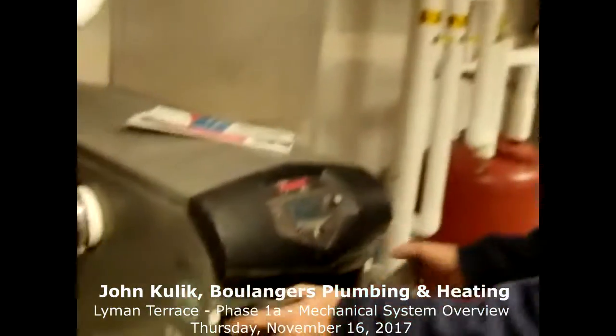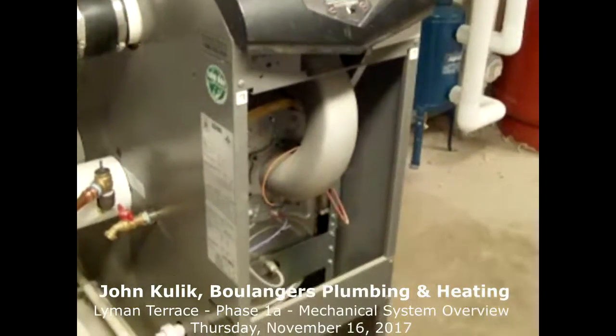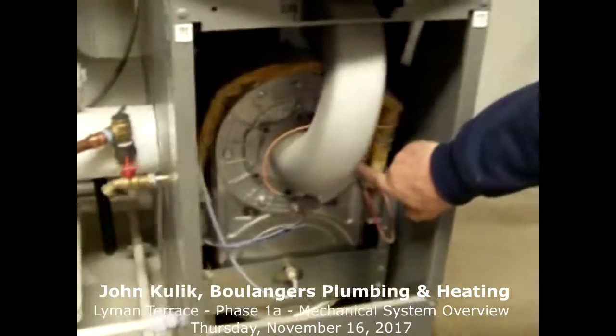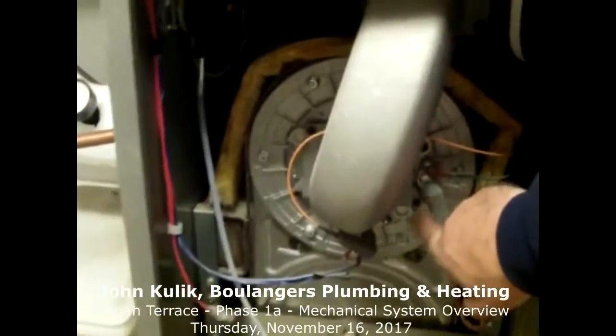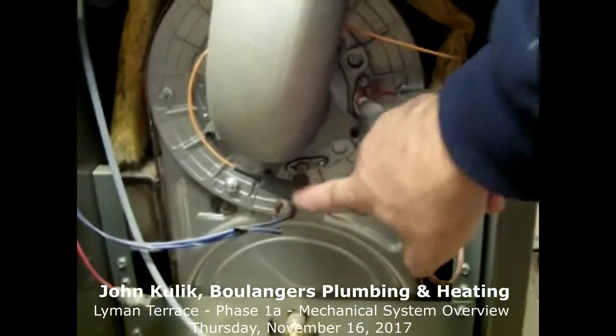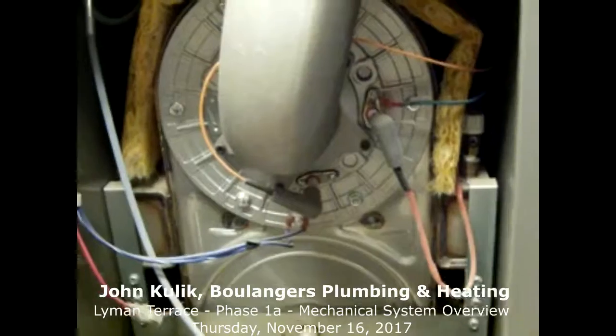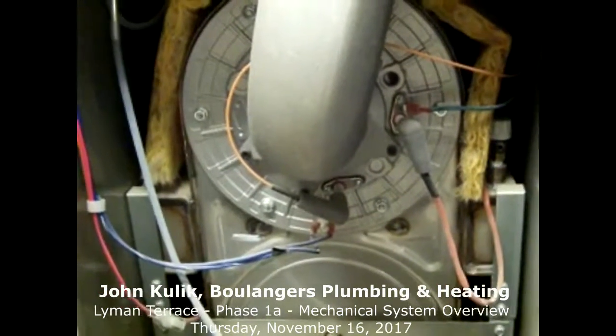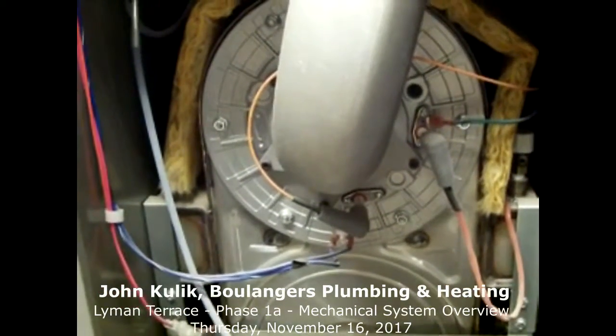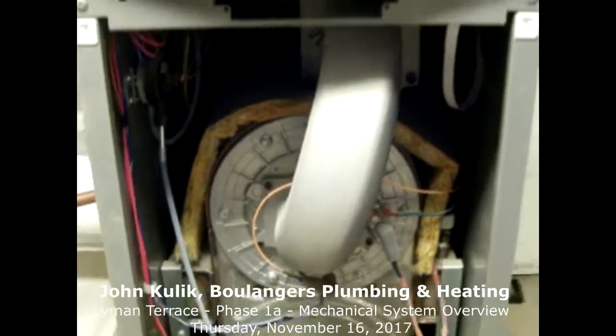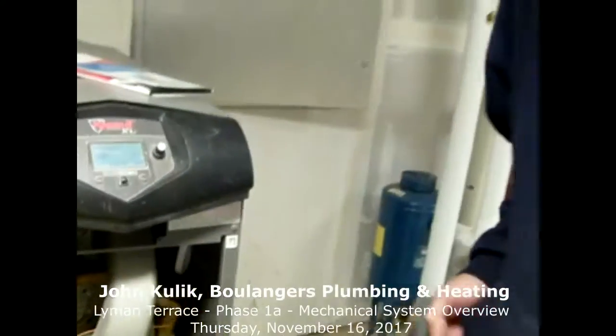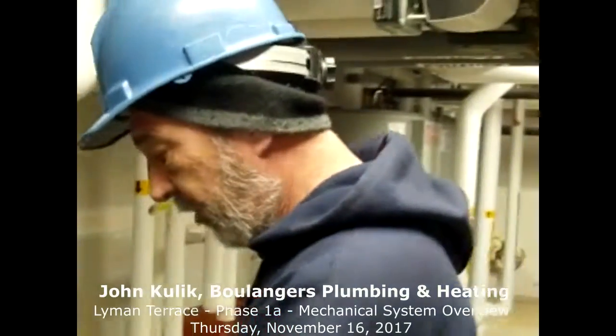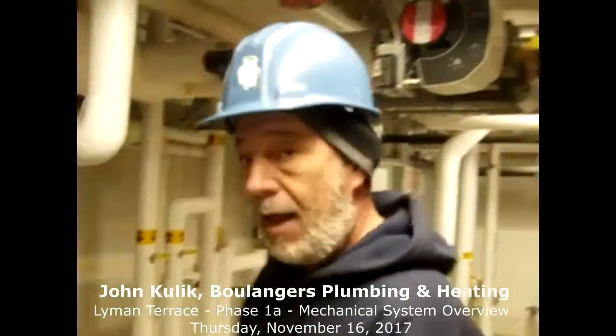Inside of the boilers also, okay, we have a spark electrode and we have a flame sensor. These here also should be checked and changed annually to keep the integrity of the system. And that's by service tech people, though. Correct. This isn't normal people. Okay. They should definitely have us come back on an annual basis and service the boilers. These boilers need to be cleaned.